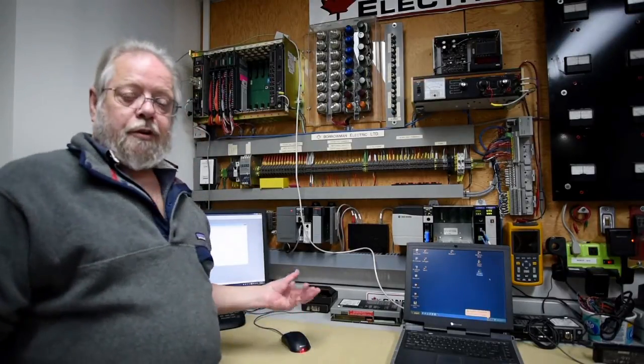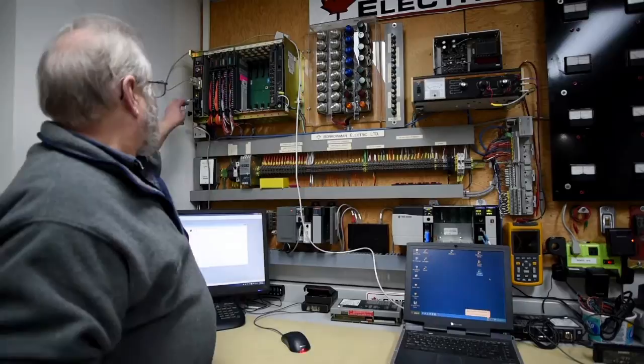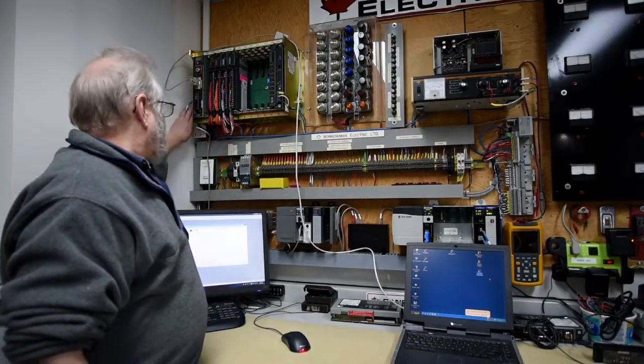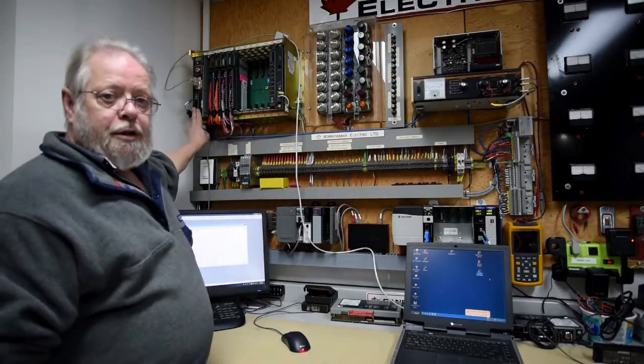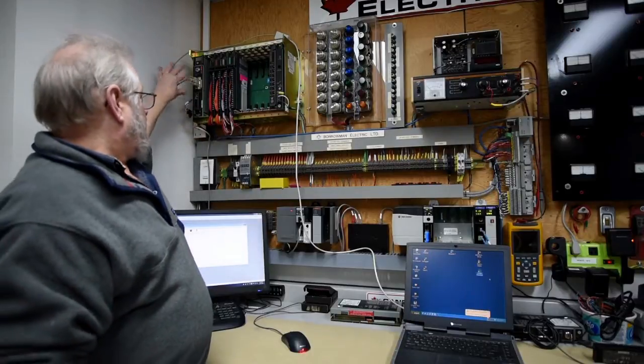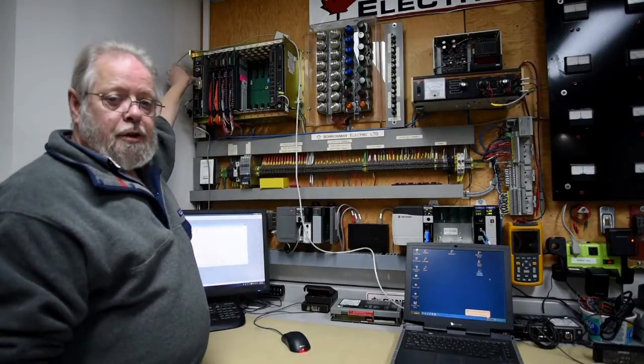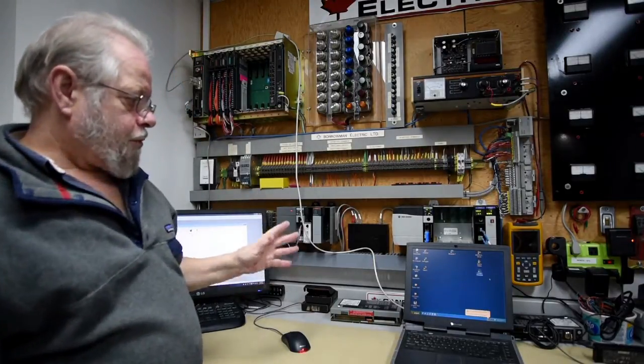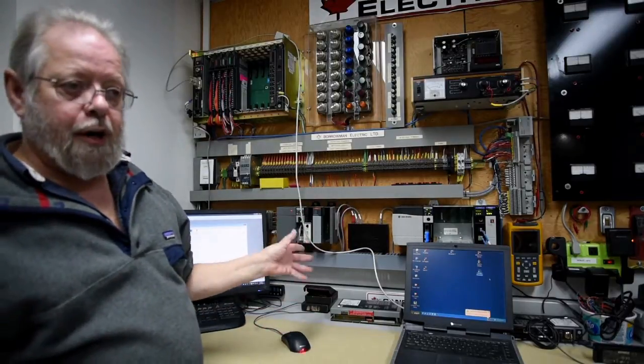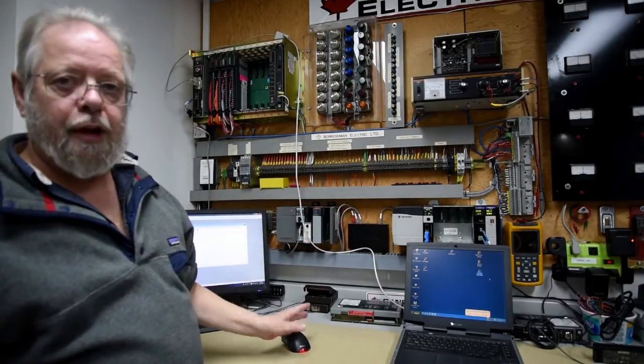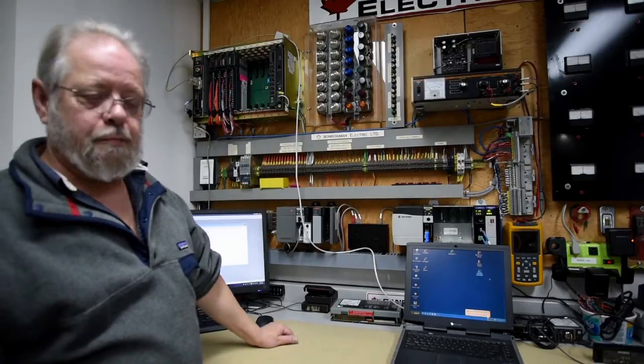So, like I say, there's a fair number of steps. We'll start out by unplugging the Data Highway. The battery is removed, and the only thing on it is the RS-232. This is a requirement of running the old ControlFlash software for this system.